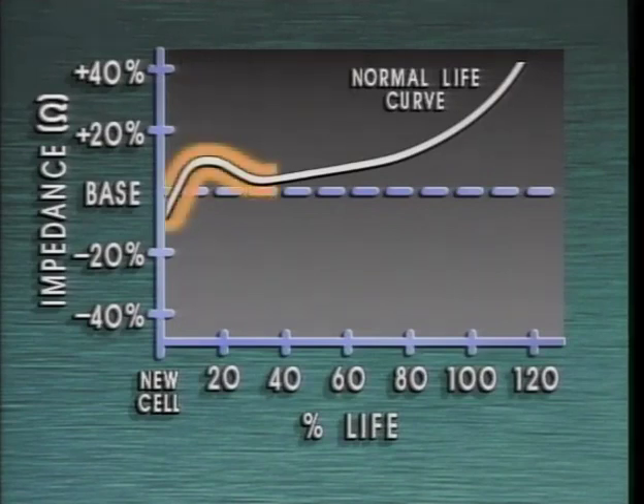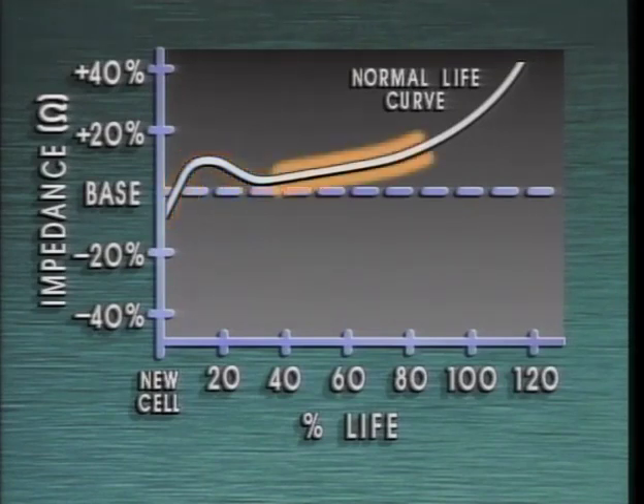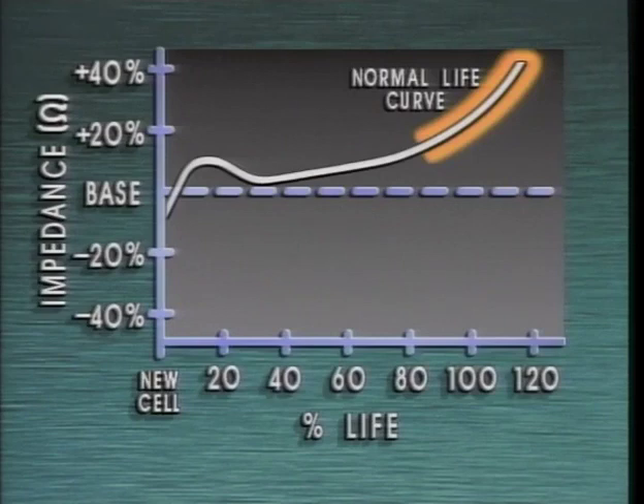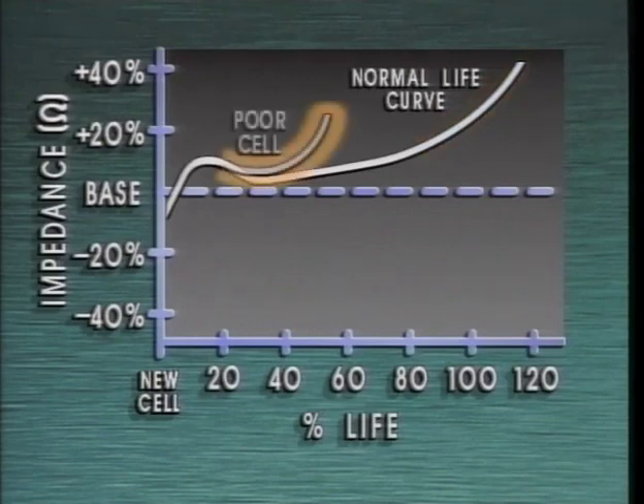During the first year or two, cell impedance varies some and finally settles to a baseline value. Then the impedance slowly rises as the cell ages and the plates sulfate from use. In the final stages of the cell's rated life, cell impedance increases dramatically over a relatively short period of time as the cell rapidly loses capacity. A cell that ages and loses capacity prematurely will show a rapid increase in impedance during the earliest stages of its rated life.